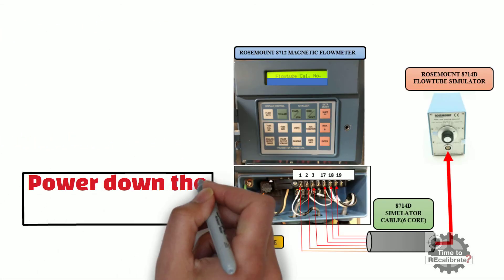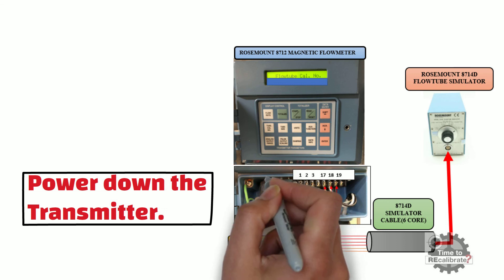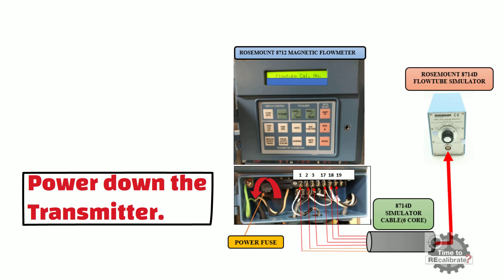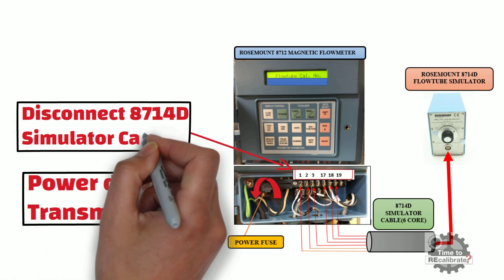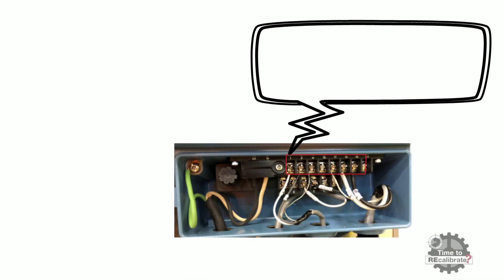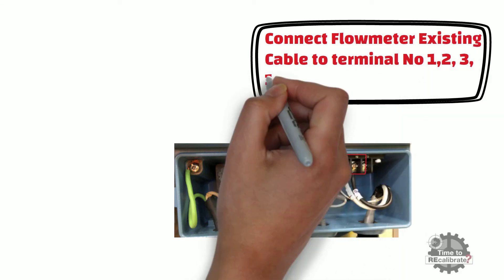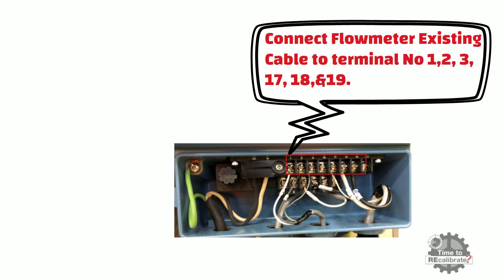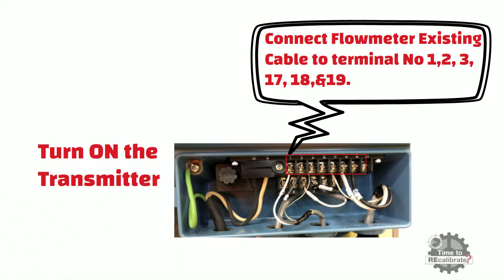Step 10: Power down the transmitter by rotating the power fuse in the counterclockwise direction. Step 11: Disconnect the 8714D simulator cable from the transmitter. Step 12: Connect the flowmeter's existing cable to terminal numbers 1, 2, 3, 17, 18, and 19. Once the connection is done, turn on the transmitter by rotating the power fuse in the clockwise direction.